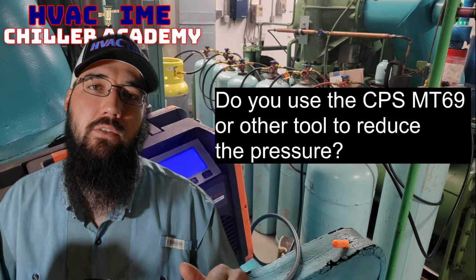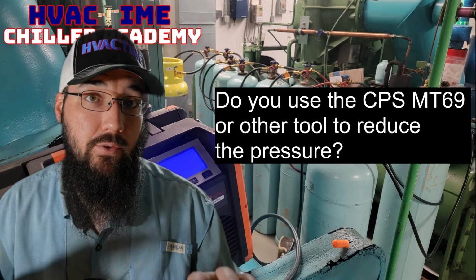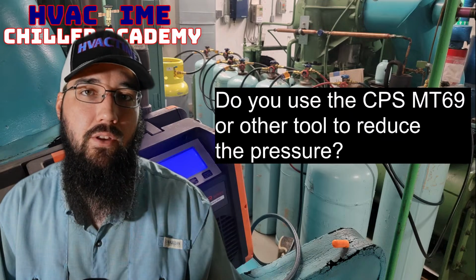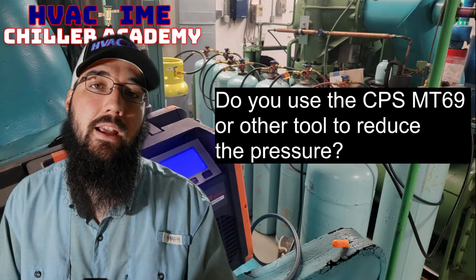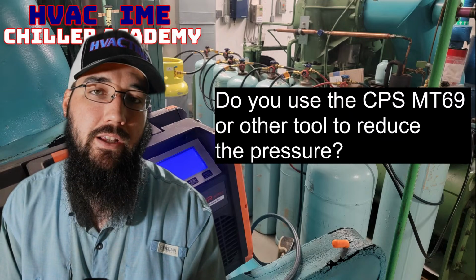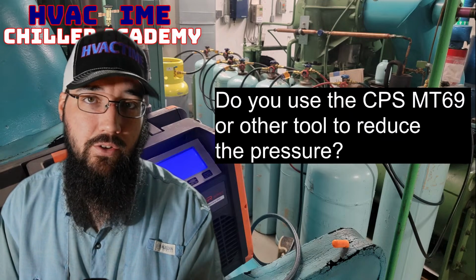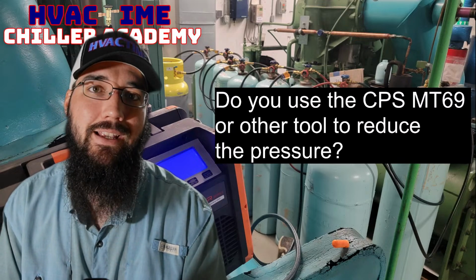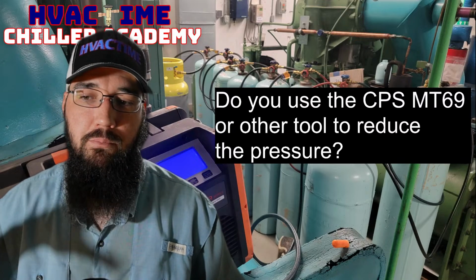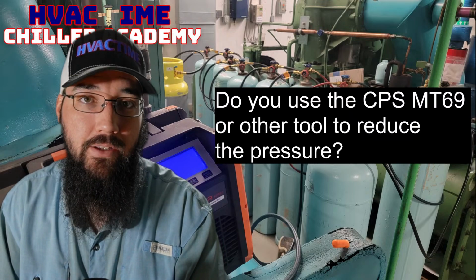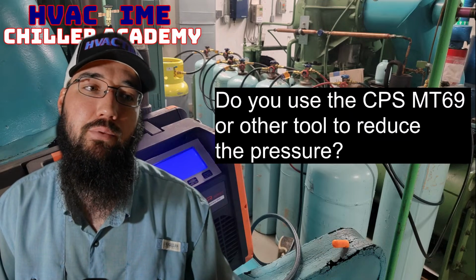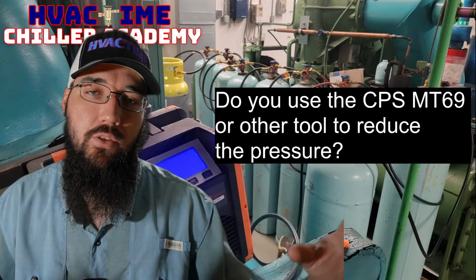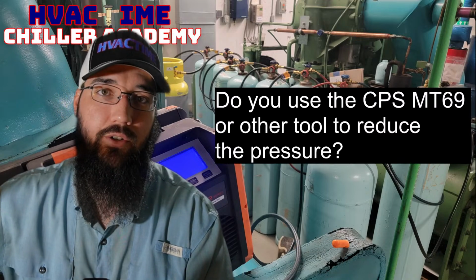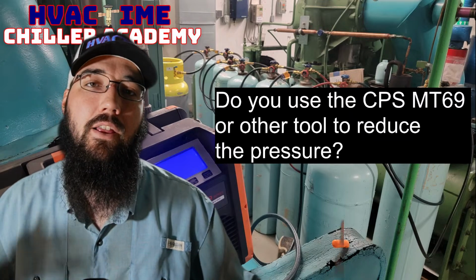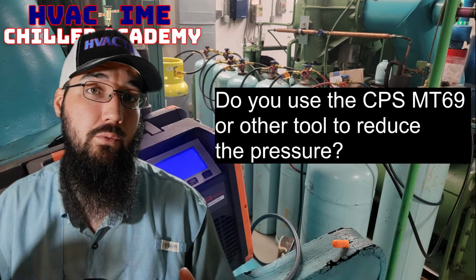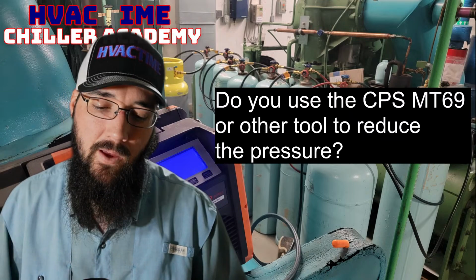Really, the main objective is to de-superheat the heat of compression that is added through the recovery machine, and then compressing more and more refrigerant into the recovery cylinder that we're using. Like, that is our ultimate issue. Between not only cramming more refrigerant into that same space, but also the heat of compression we get from the recovery pump, those two things cause a lot of pressure and heat to build up in our cylinder. That slows down, if not brings our recovery to a complete stop in some cases.